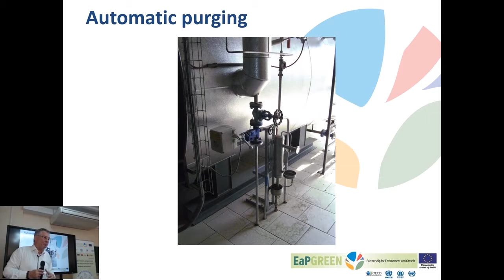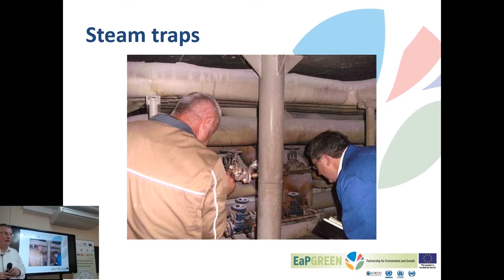Here we are checking condensate traps, because when steam heating, we have condensate traps to separate the steam from the condensate and allow only condensate to flow through the return pipes to the boiler, keeping steam to heat wherever I want it in the heating coils or heating jackets. We are checking here whether these condensate traps work, because after a while, say 2-3 years, they will fail and need to be repaired or replaced.